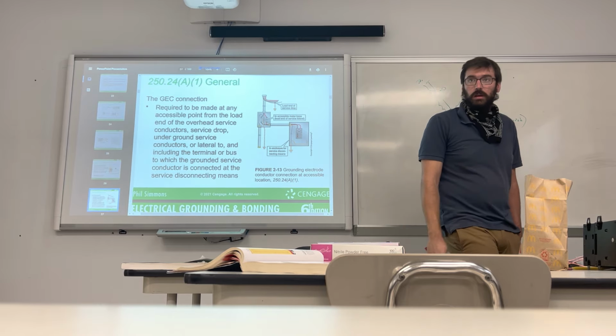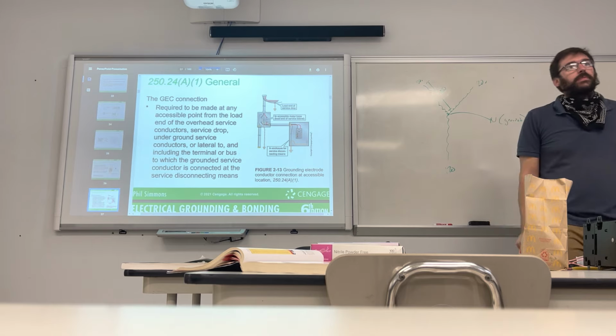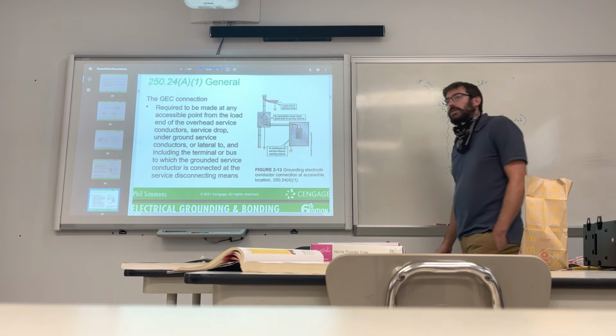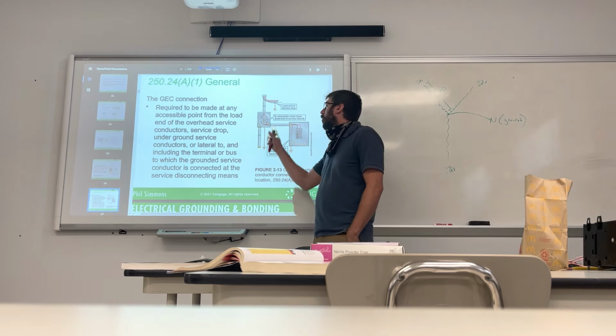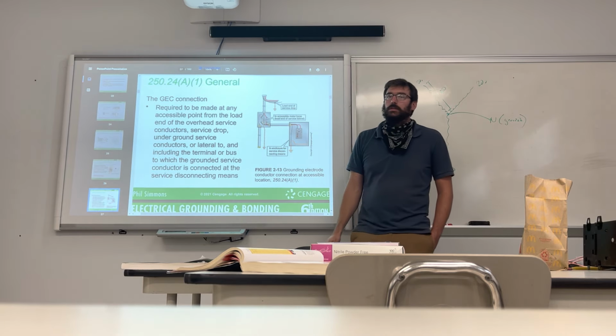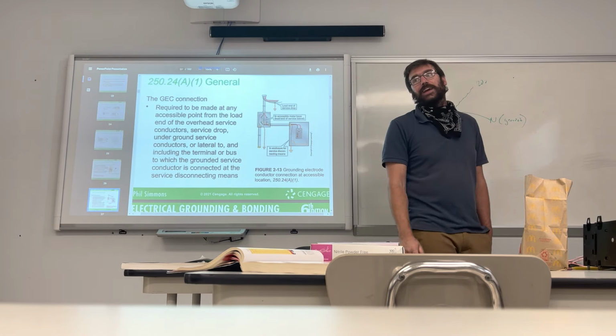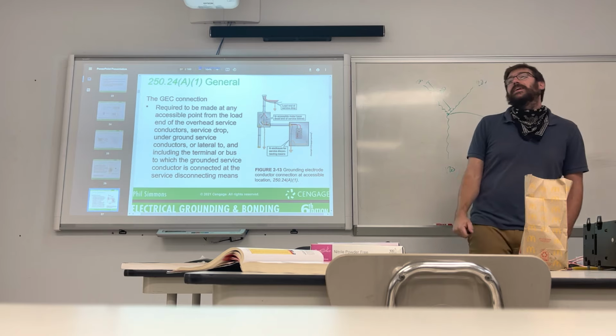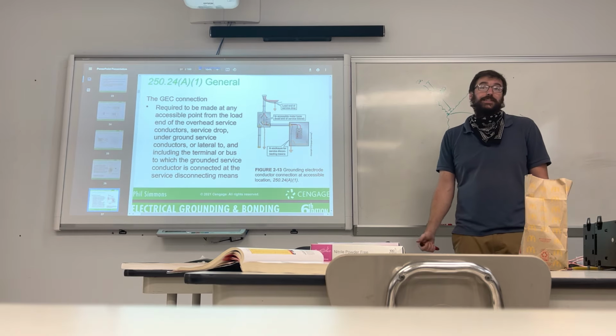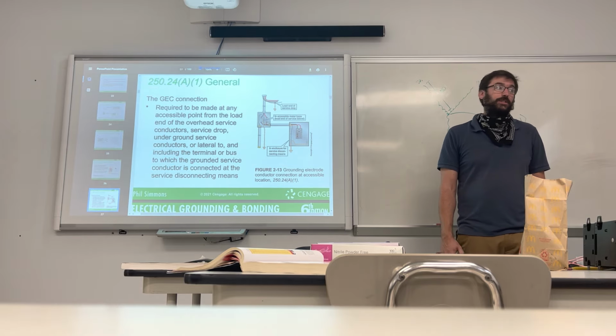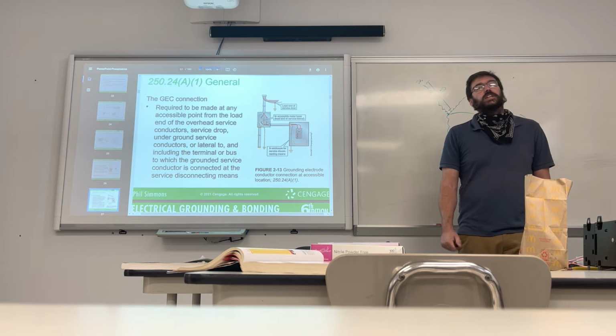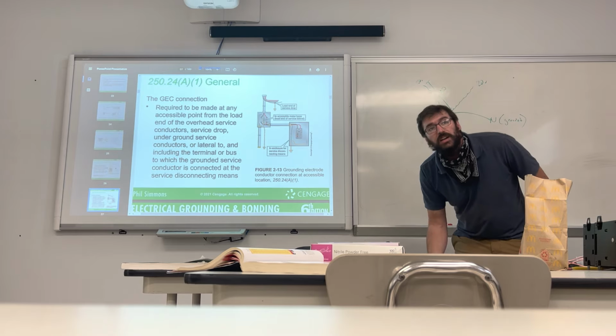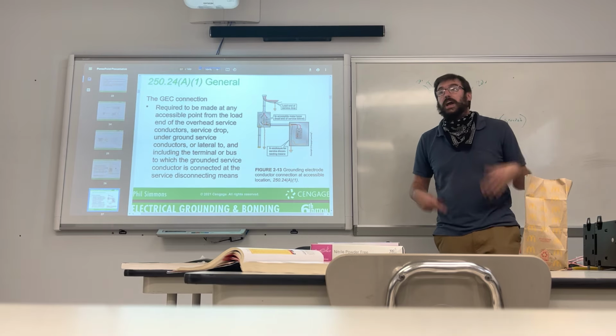Is it? If I wanted to look at that neutral and check out that ground, what would I have to do to that meter? Pull the meter, I have to pull the meter. And then what happens the second I pull the meter? Lose power. Should I have to kill the power to be able to inspect something? No. So is it really accessible? No. Is it accessible to service it? Hell yeah. If I'm servicing it, I have to do what I have to do.